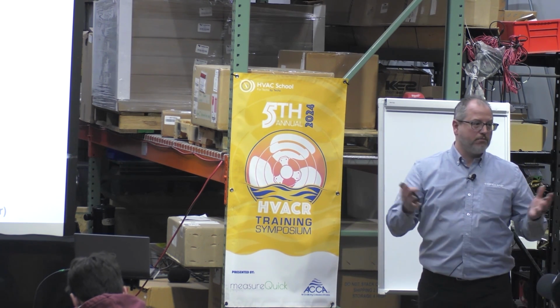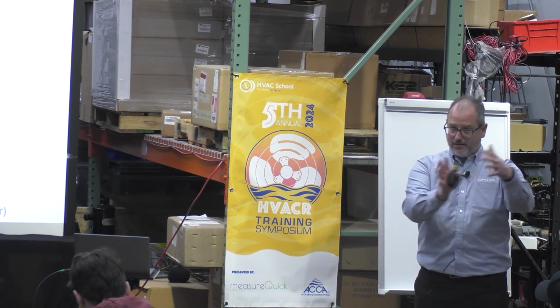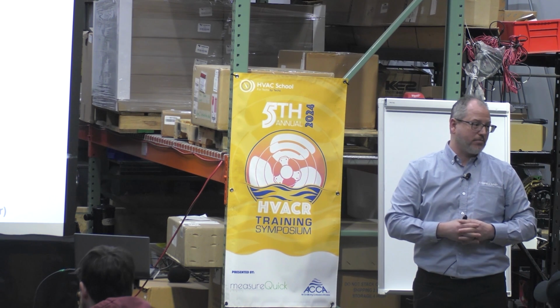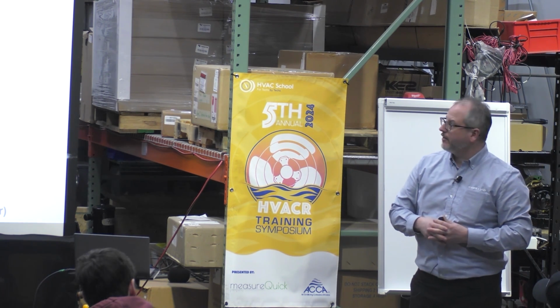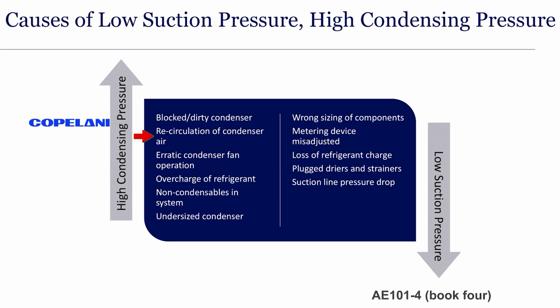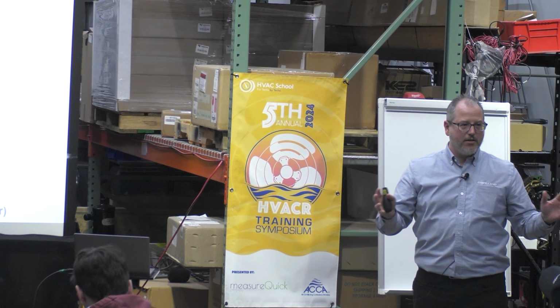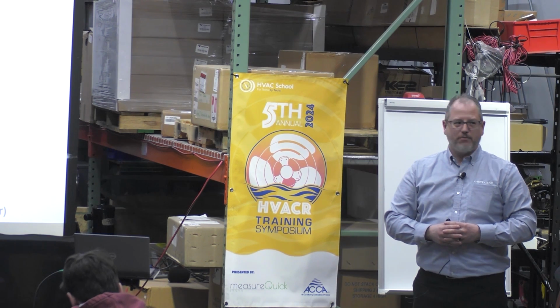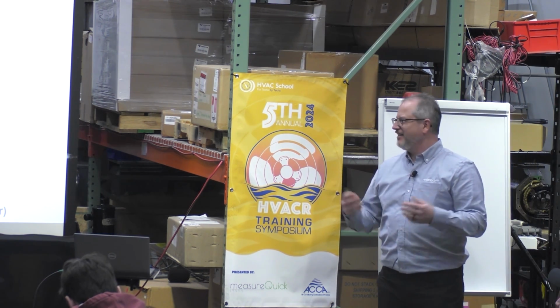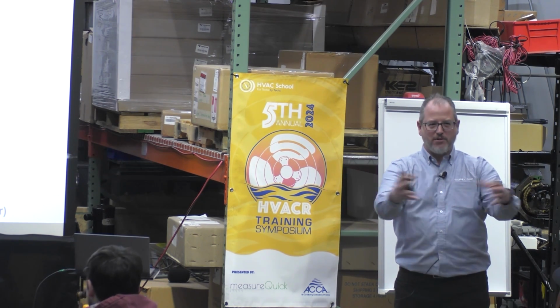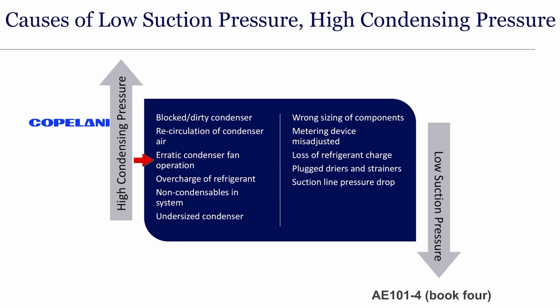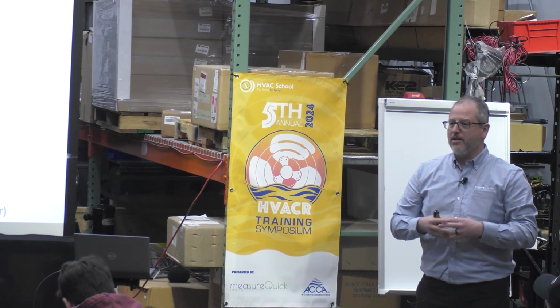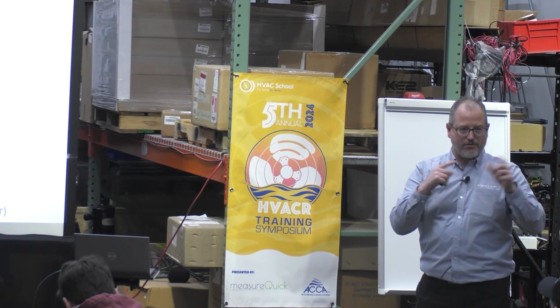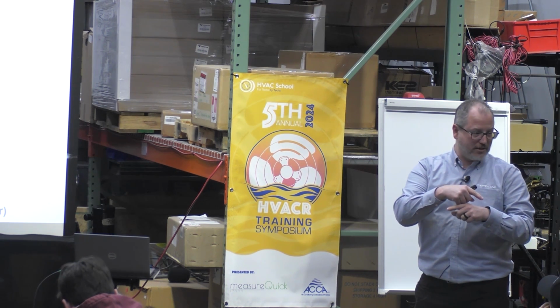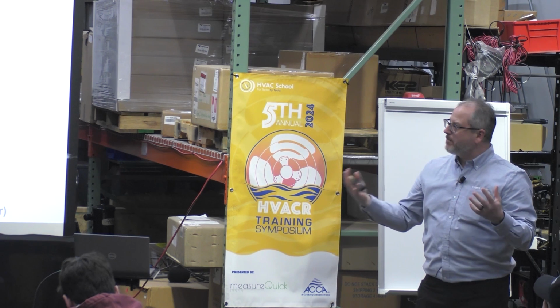Or if you look at a lot of mini splits, a lot of those will have 2 or 3 pass condenser coils. You have to split those apart, so make sure everything is clean in there. Recirculation of condenser air. Have we seen that before, where people like to put their shrubbery around the condensing unit or put a deck or porch? Yeah, you name it. I think it should be in the center of the yard, right? They're beautiful, right? So, condenser fan operation. We get these one-size-fits-all condenser fans, and you can rotate the speed, so you can change the wiring, which changes the direction. So who knows if somebody put the fan blade on the right direction anyway, or if it's going in the right direction. So you have to be paying attention with all that.